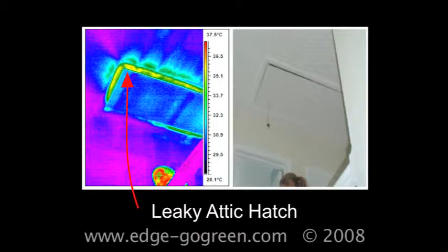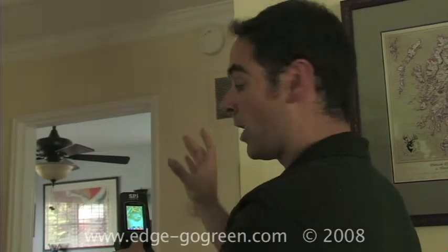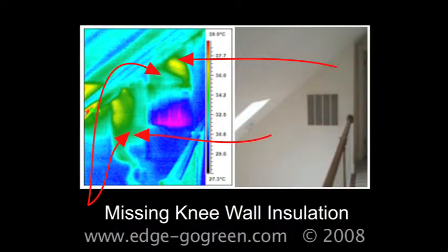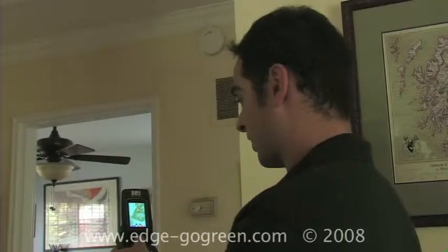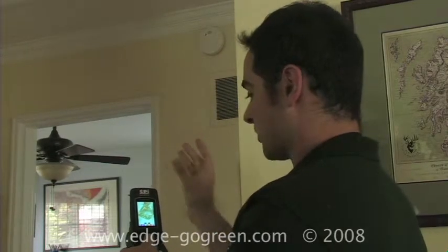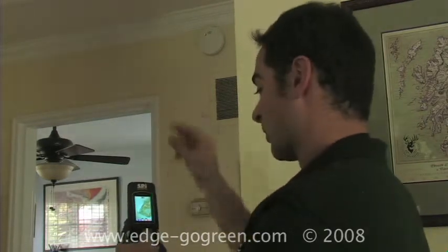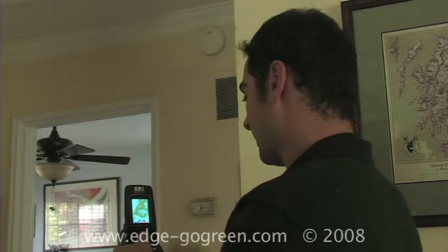If we're looking on here and we see any spots that are completely warm, just solid warm spots, that's usually missing or low levels of insulation for us, and what we'll do is identify those and we'll get up in the attic space afterwards to visibly see that. But normally we're looking for any cold or, in this case, warm areas. Just single spots are basically low levels of insulation, and streakage patterns are areas where there's air movement actually coming in through that. So we're looking at both convective and conductive losses.